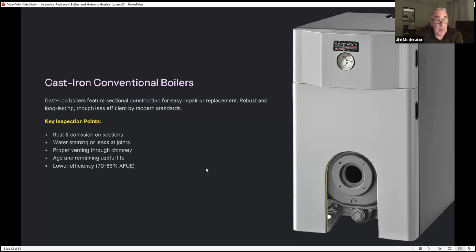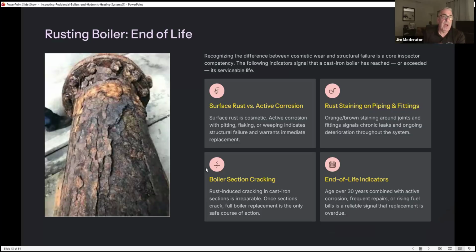Key points. What you're going to look for during an inspection is rust and corrosion, water staining or leaking at joints, proper venting through the chimney. You're going to want to determine the age and remaining useful life. These usually work at a lower efficiency, okay? 70 to 85% efficient. And I think we have pictures here.